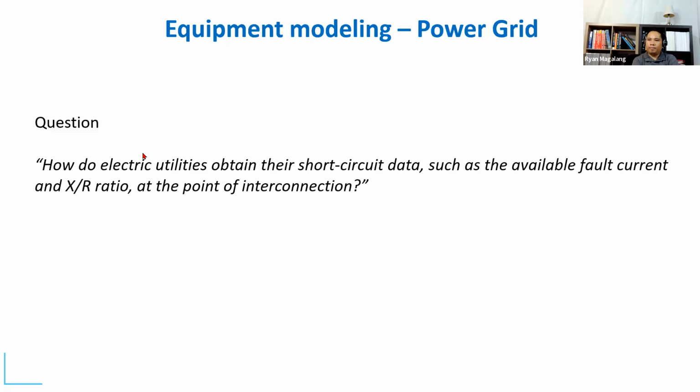It's like your ETAP or your SKM model. They would model everything, and when you ask for a fault level and XR value at a certain location, let's say point A, they would extract that from their database.